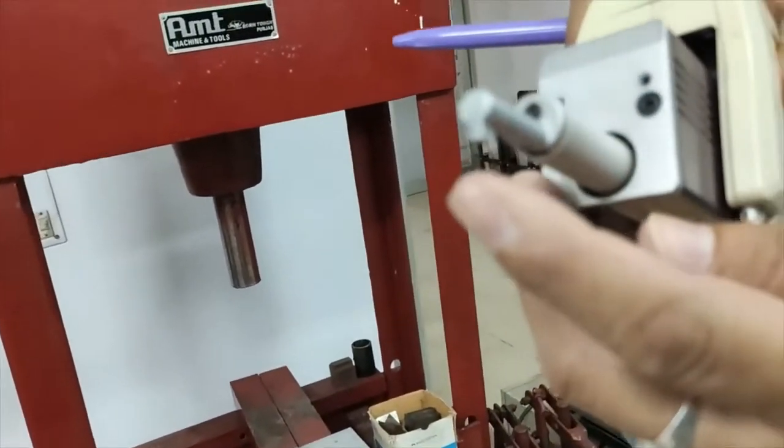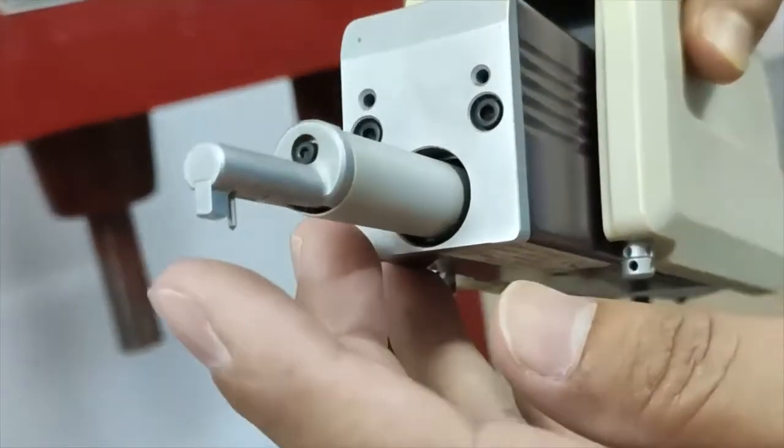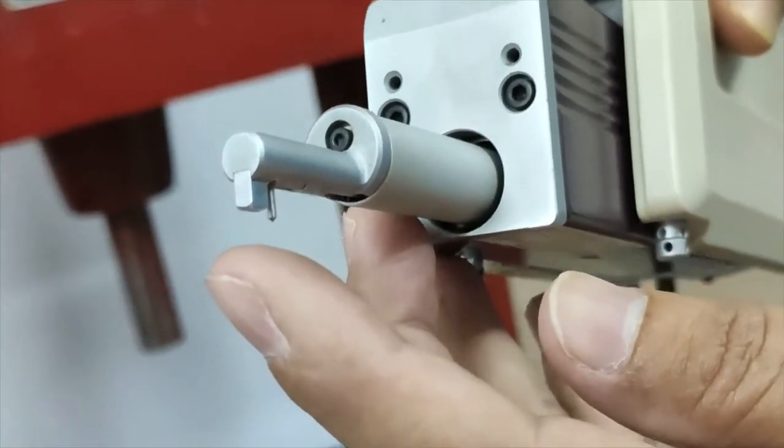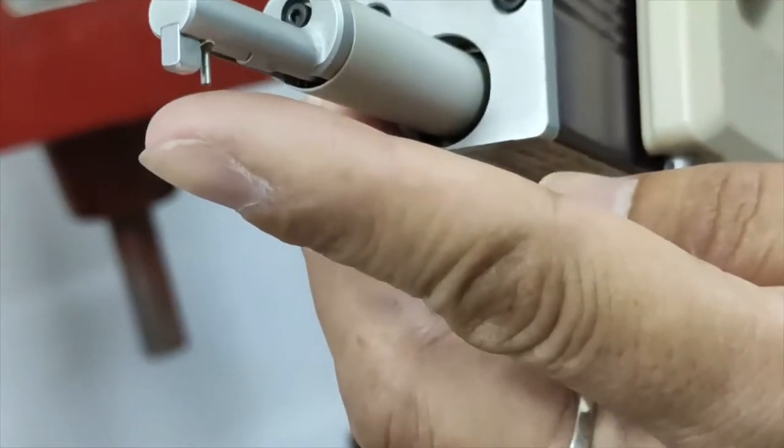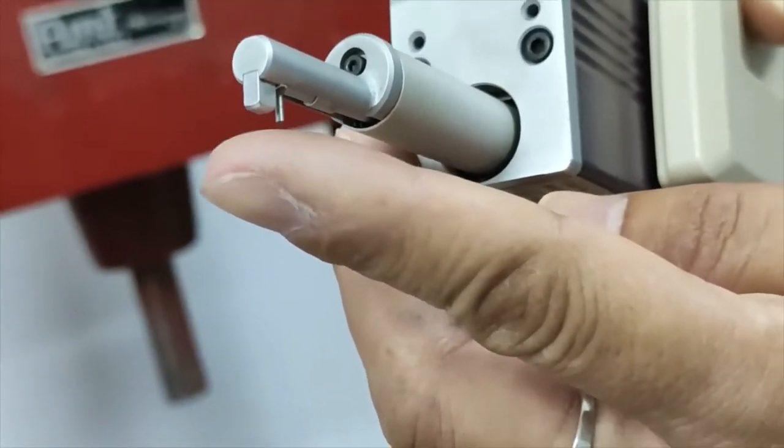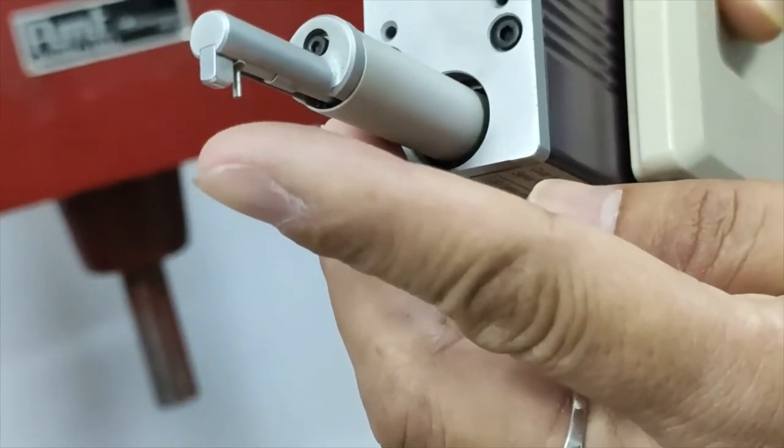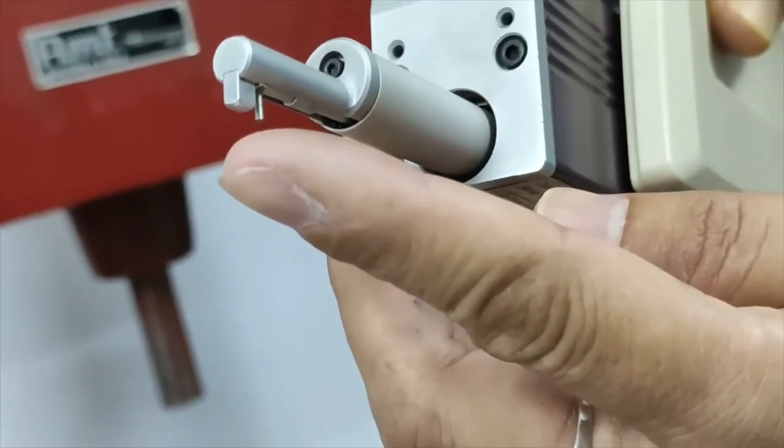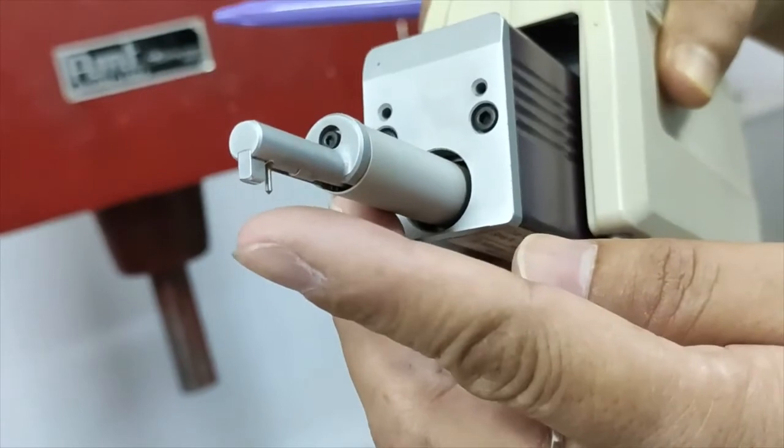Actually in principle, the stylus with diamond tip, when you keep it on the surface of the machined surface, this stylus will travel 4 mm. I am setting here 4 mm. This will travel like this 4 mm, and along with the surface it will vibrate. This vibration is converted to the roughness quality or roughness value.